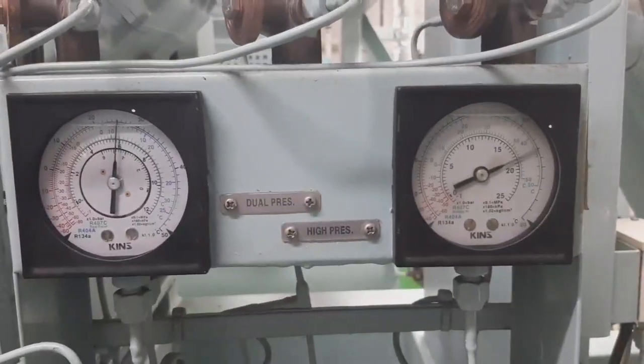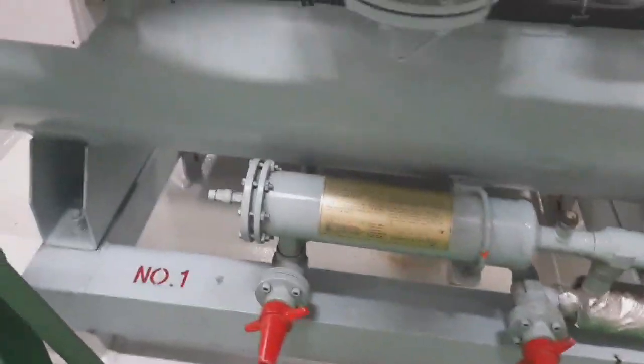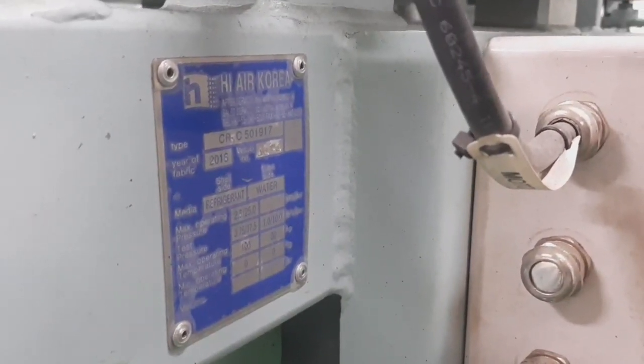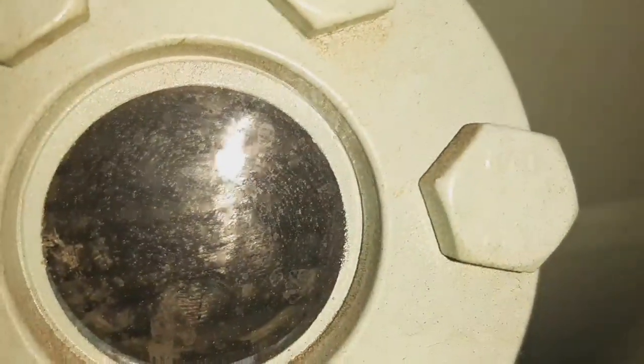This is the low pressure for system 1 — parameters are normal, also equipped with pressure switches and capacity controls. This is the dryer for system 1. This is the nameplate for our system — Hi Air Korea. This is the name of our system. This is the sight glass for system 1 — as you can see, there is enough refrigerant.